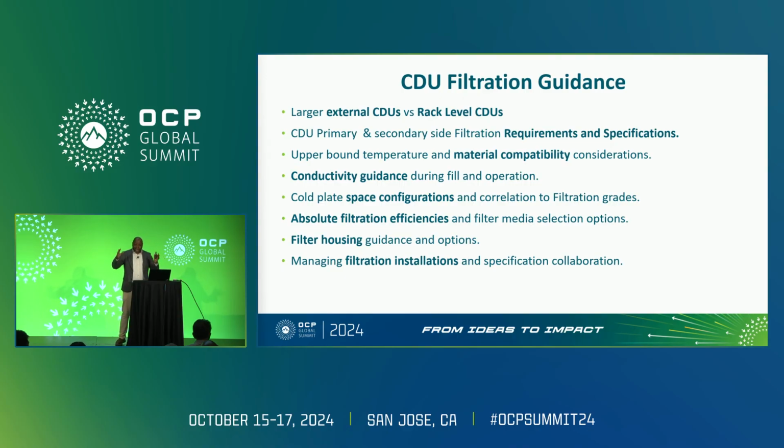Okay, just one person, and that's a big problem. Like guys, you really should know what the efficiency of your filters is, because let's say you've got two products, they're both 25 micron filters. One could be 50% efficient, the other could be 99.98% efficient. The performance of those filters would vary drastically, and the 99.98 would knock out, as I said, the majority of particles, whereas the 50% efficient filter would let in 50% of all the particulate in your fluid stream. So it's not really doing its job.